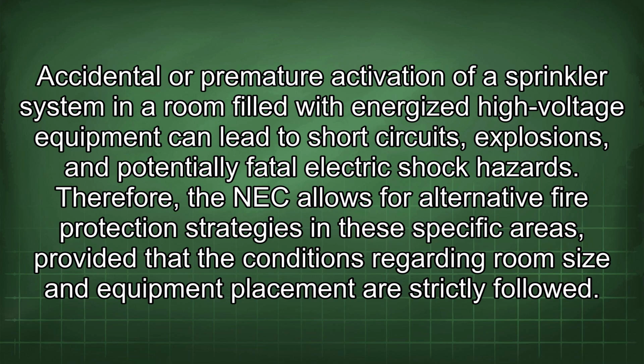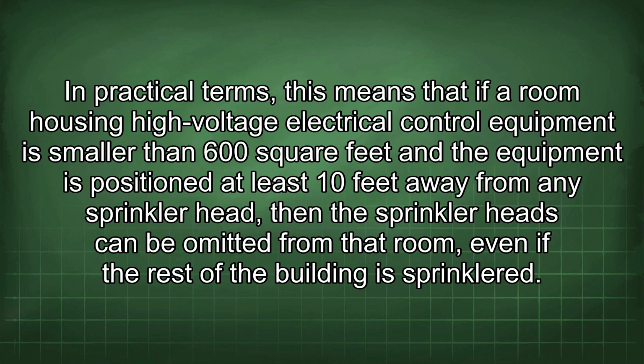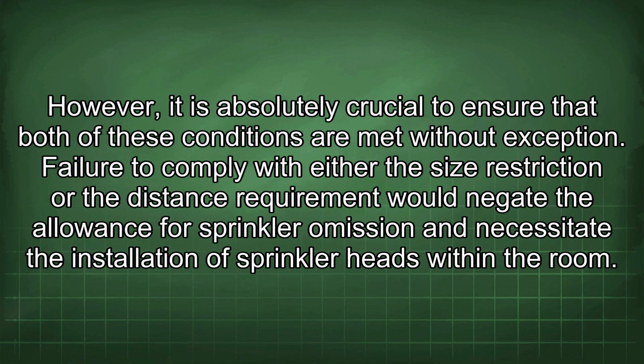Therefore, the NEC allows for alternative fire protection strategies in these specific areas, provided that the conditions regarding room size and equipment placement are strictly followed. In practical terms, this means that if a room housing high-voltage electrical control equipment is smaller than 600 square feet and the equipment is positioned at least 10 feet away from any sprinkler head, then the sprinkler heads can be omitted from that room, even if the rest of the building is sprinklered. However, it is absolutely crucial to ensure that both of these conditions are met without exception. Failure to comply with either the size restriction or the distance requirement would negate the allowance for sprinkler omission and necessitate the installation of sprinkler heads within the room.